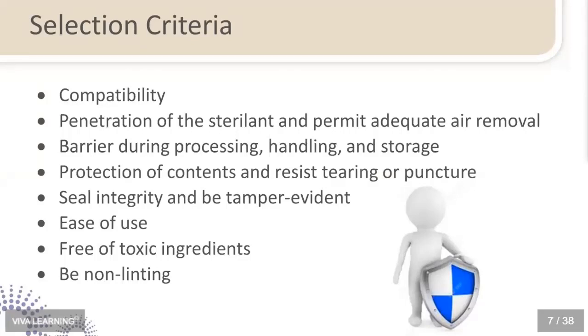Here's a thought. In dentistry, we tend to use sterilization wrap, the blue wrap, and or plastic paper peel pouches most often. When you're thinking about peel pouches, the only side that the steam sterilization can enter on a peel pouch is the paper side. The laminate or the plastic is impervious, and steam is not going to enter there. You want to make sure that the quality of the materials that you're selecting are in fact going to be able to provide an adequate barrier or protection against tearing or puncture.